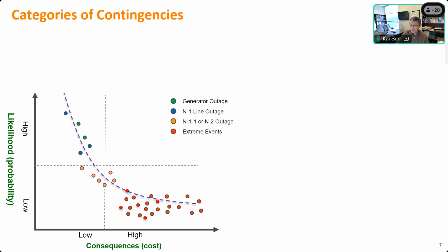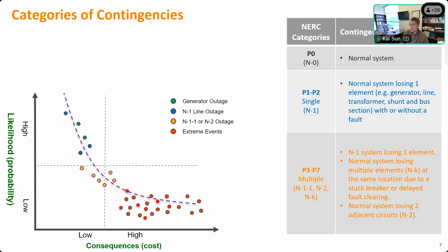If we compare those contingencies to the existing categories defined by NERC, NERC currently defines P0, P1 to P2, and P3 to P7. P0 basically means a normal system—there are no contingencies at all, it's N-0. P1 to P2 basically means N-1, meaning you just lost a single component. So it's a normal system losing a single element—it can be a generator, line, transformer, or maybe a bus section or shunt.